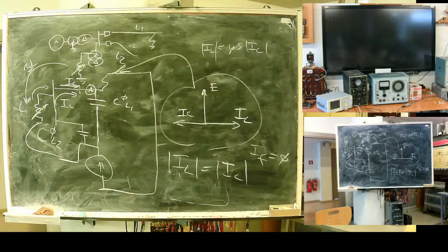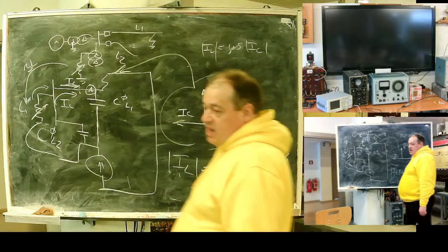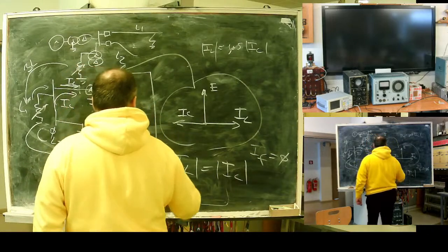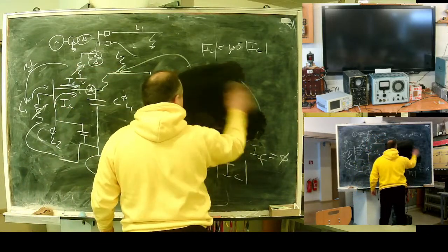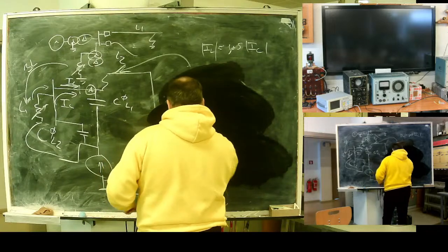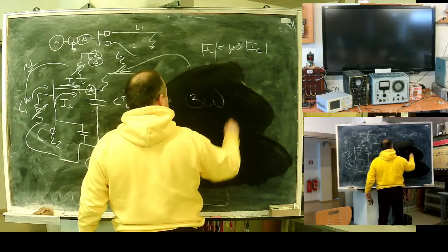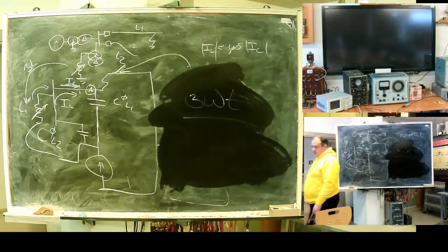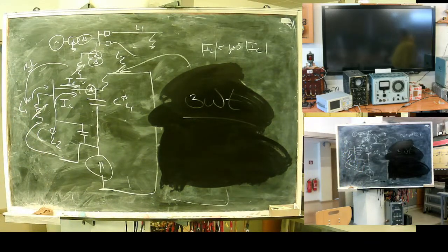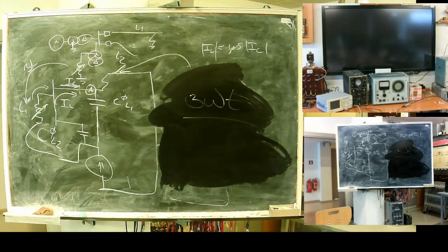Another solution is usage of higher harmonics. Using 150 Hertz component, third harmonic. In case of third harmonic, there will be no compensation. Petersen coil reactance will be triple, and capacitance, capacitive reactance will be 1/3. So no compensation, direct.